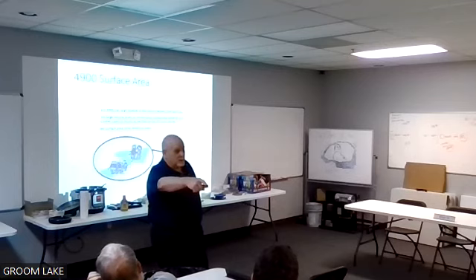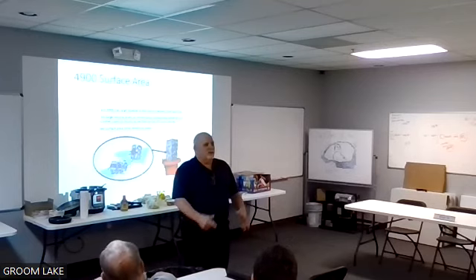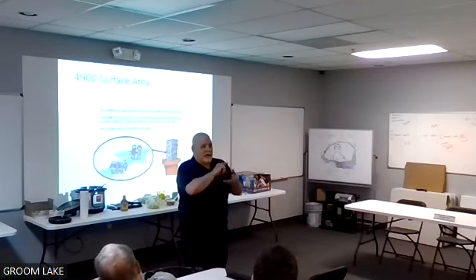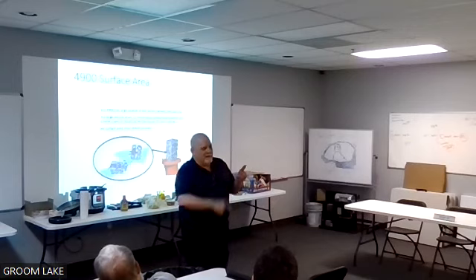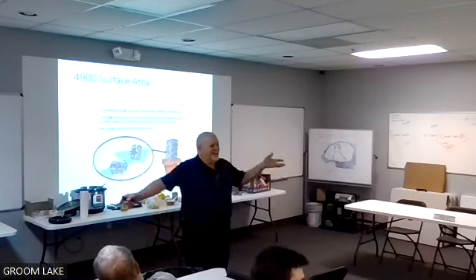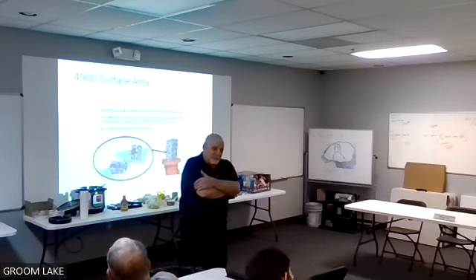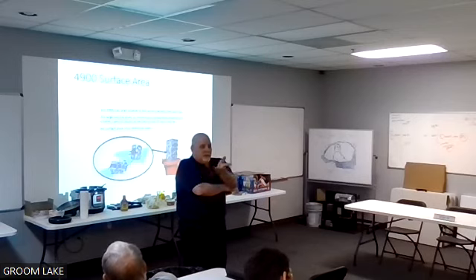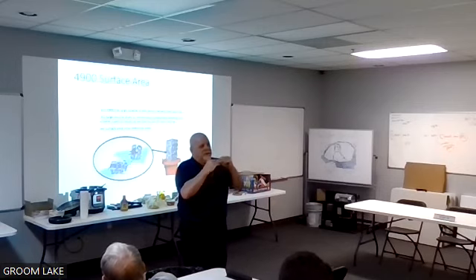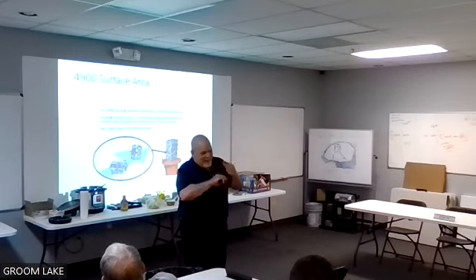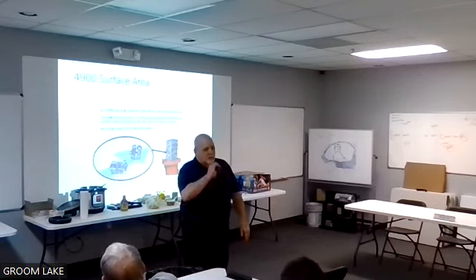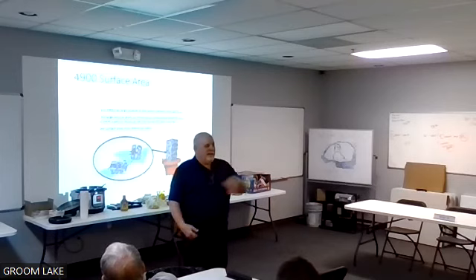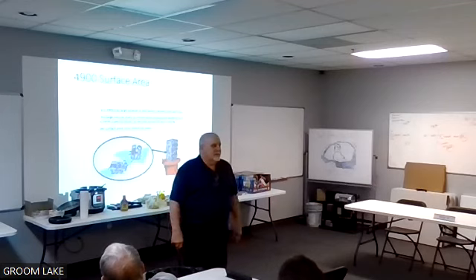Well, that's exactly what the flow throughs do. Instead of that water just sitting captive in there and not moving and developing Legionella, these new flow throughs actually bring water in and circulate that tank the entire time it's expanding and contracting. How did we even survive drinking from the hose? Exactly. But good, I'm glad you brought that up. I did not think to put that in my presentation. I will next time. If you look on Taco's website, they're called flow through. They just have a different head connection, like a T connection on top. It still allows it to expand and contract, but it allows water to circulate in that tank. As the water moves in and out, it's turning that tank over every time. So it's not stagnant, and it gets the water moving so it won't develop Legionella. That's the whole idea behind it. Very astute. You get a gold star.